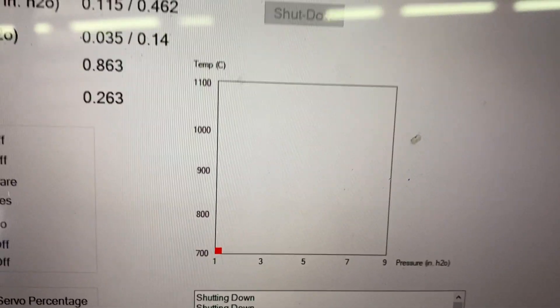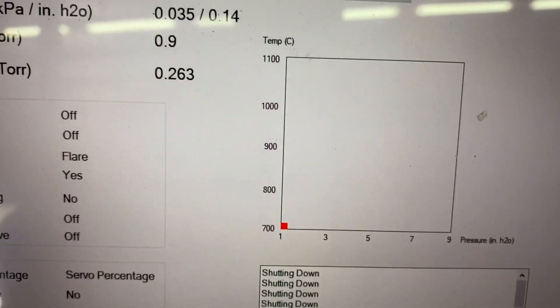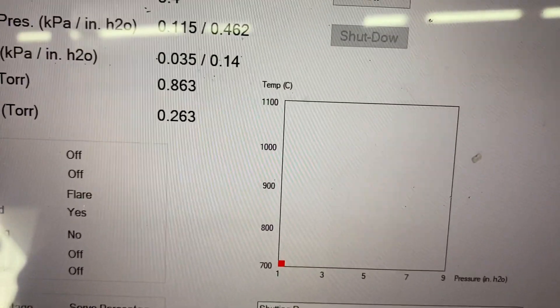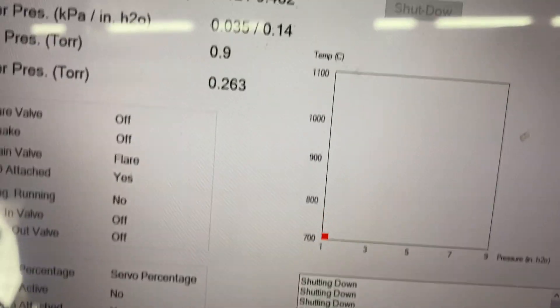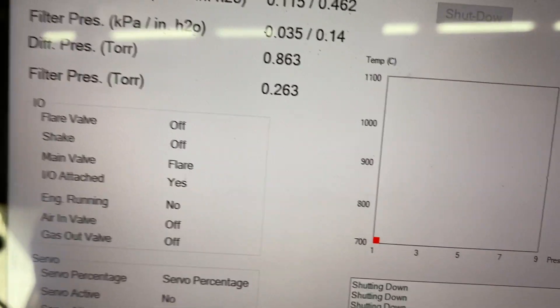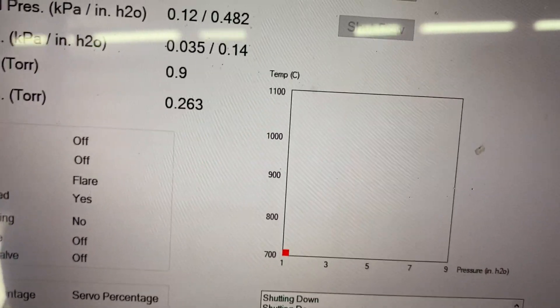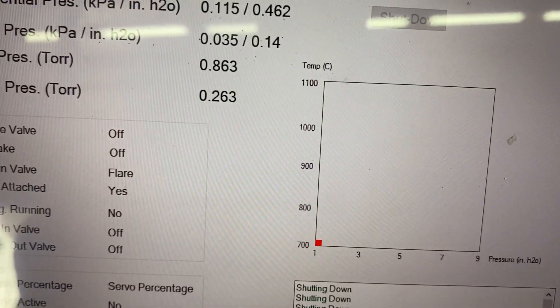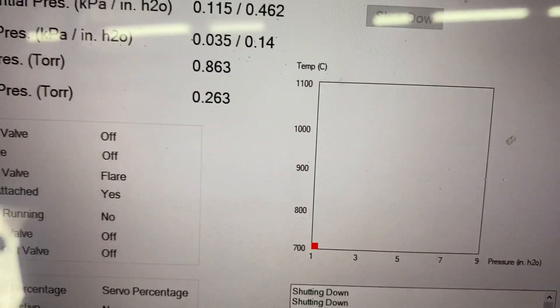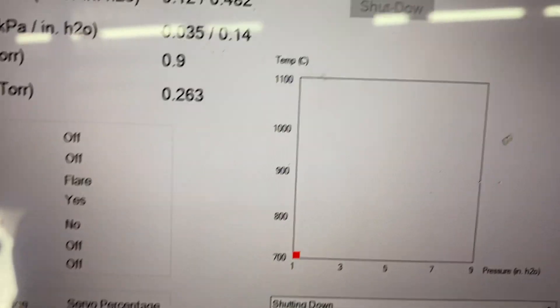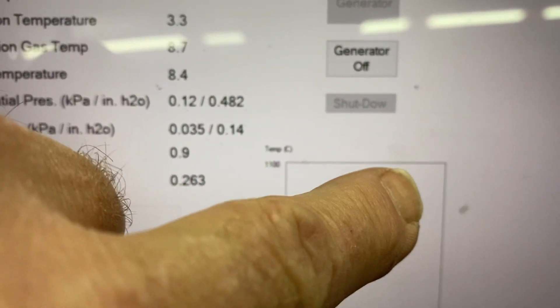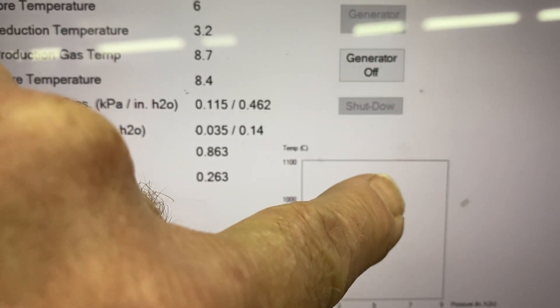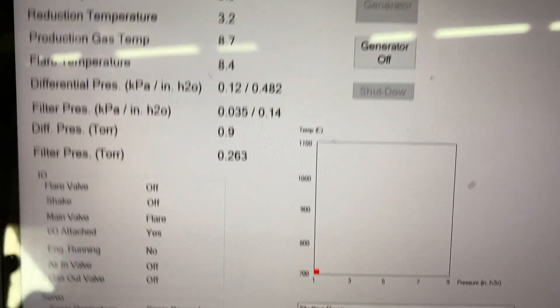So when this is running, when everything's optimized, you'll see this red dot float right to the middle of the chart. Right where it should be. So somewhere, actually a little higher, somewhere around 1,000 to 1,100 would be combustion chamber. And then differential pressure can creep up to like seven inches of water or so. So you'll see the red dot show up there somewhere.